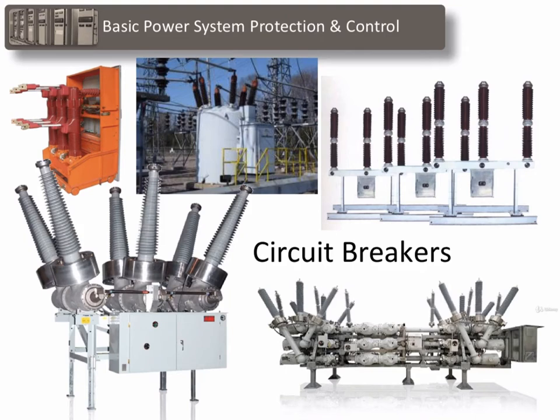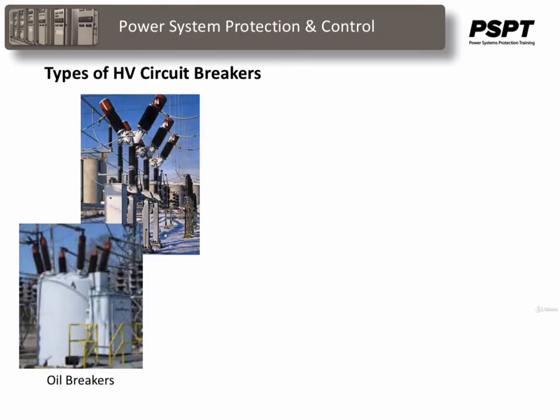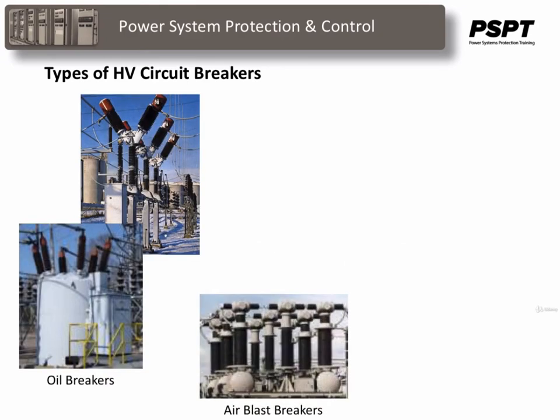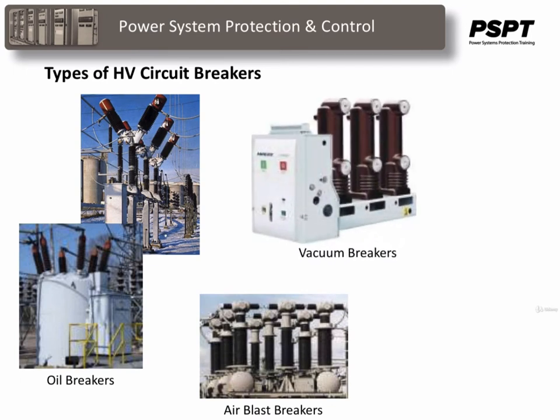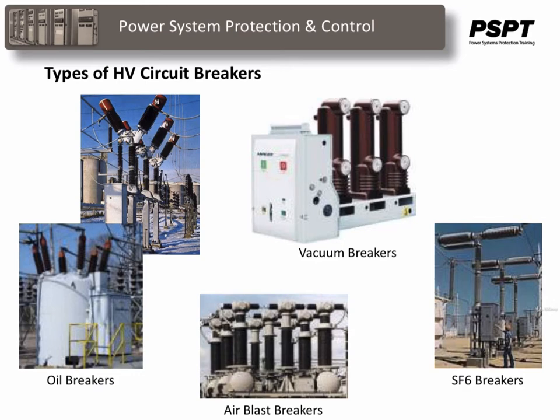We're going to go through a few of the major circuit breaker types that are out there. And again, a lot will depend on the interrupting capacity that is required, the speed with which you need to operate the circuit breaker, and the voltage level of the circuit. Most of the high capacity, high voltage breakers that are out there today can be divided into one of four categories. They are either oil breakers, air blast breakers, vacuum breakers, or SF6 breakers.